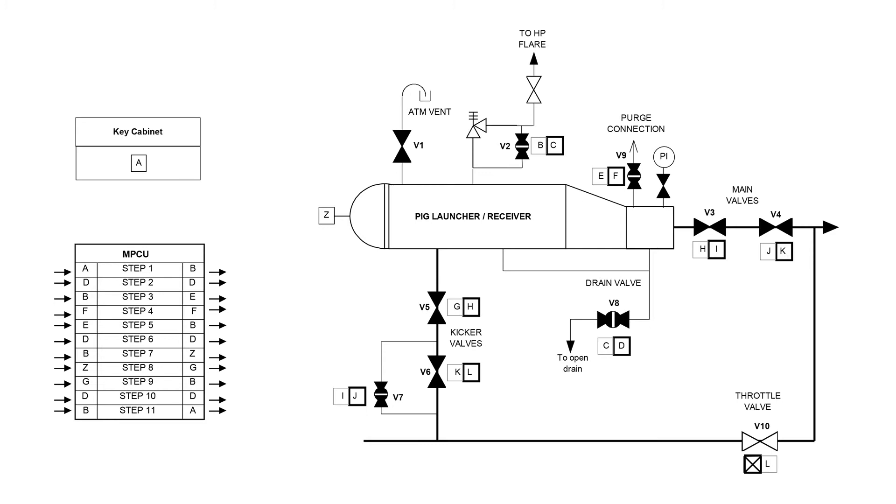Pigging systems are commonly equipped with interlocks to make sure that the vessel can only be opened when it is isolated, vented and drained. The start key A is locked in the cabinet. As can be seen, the key position in the cabinet only allows key A to be entered. Every other key should remain in the field.